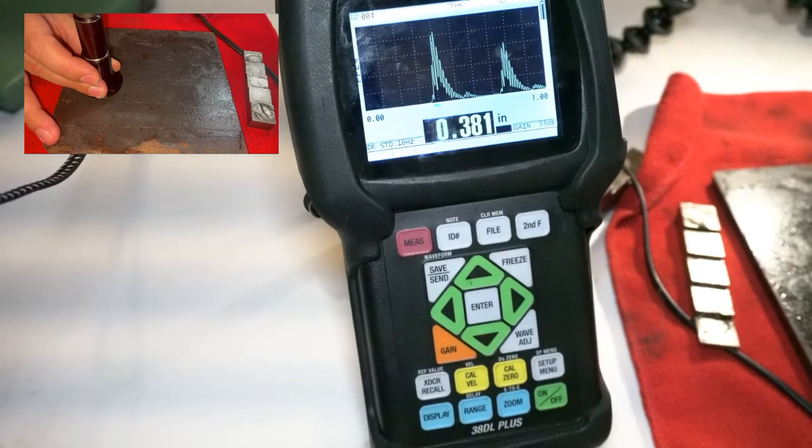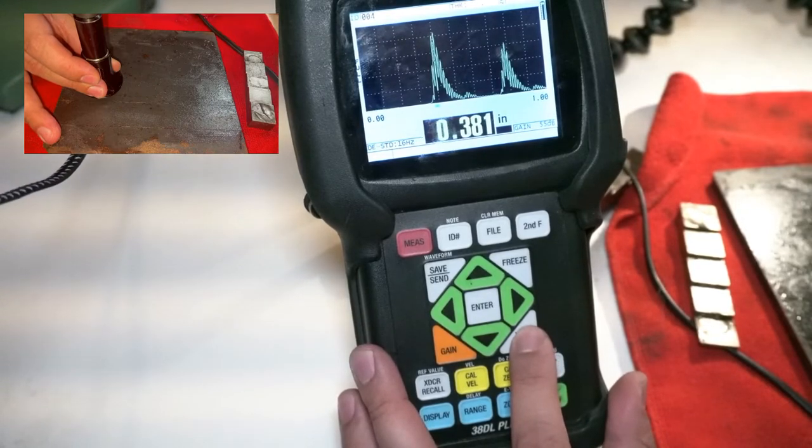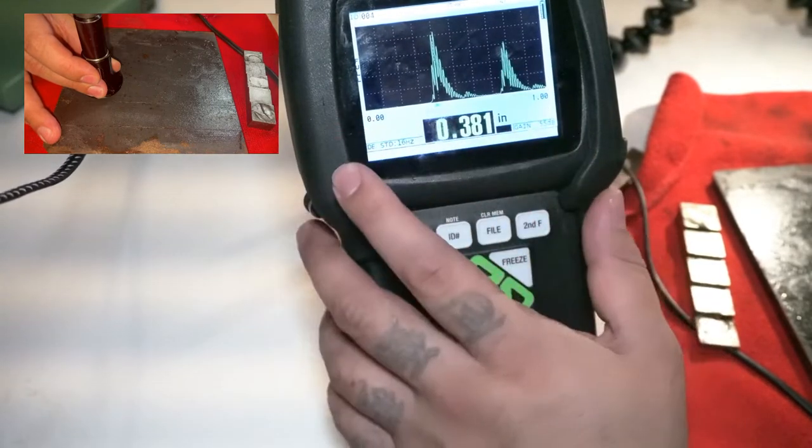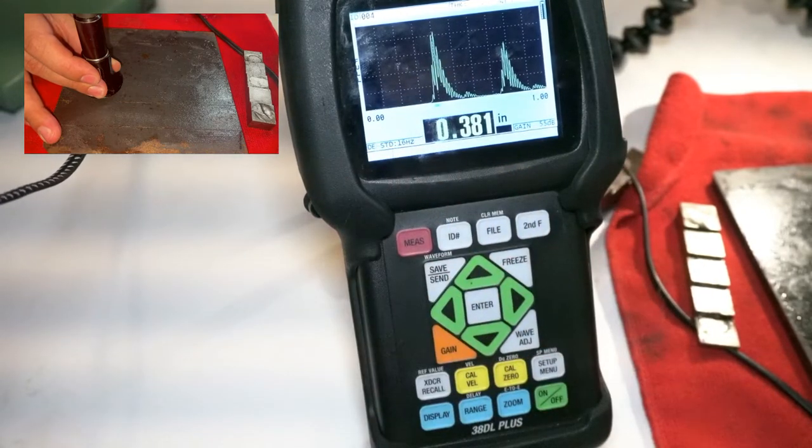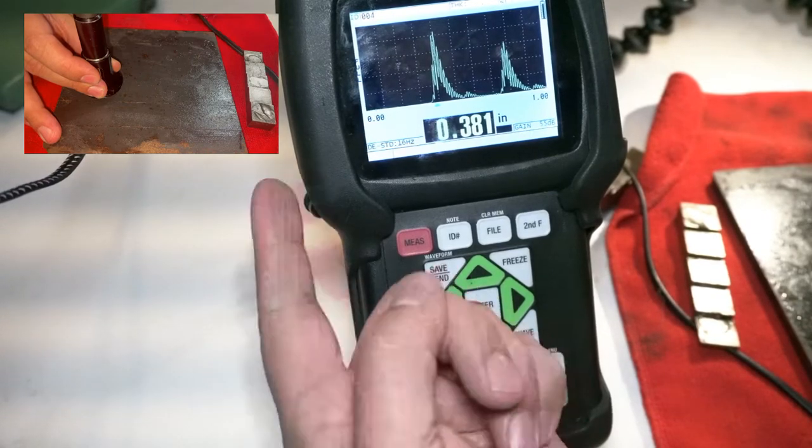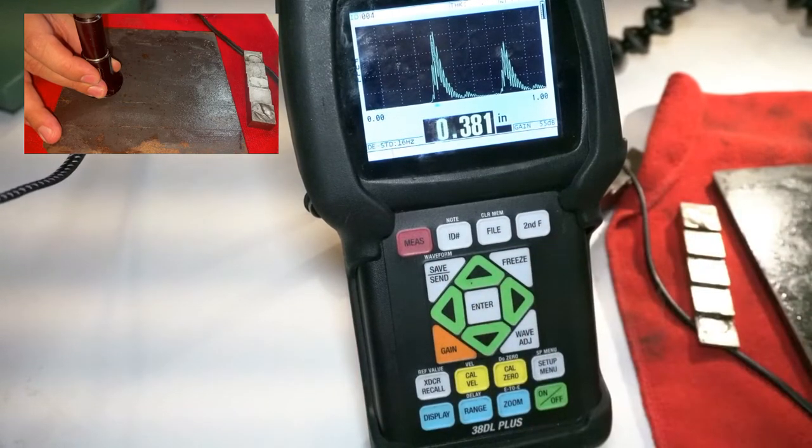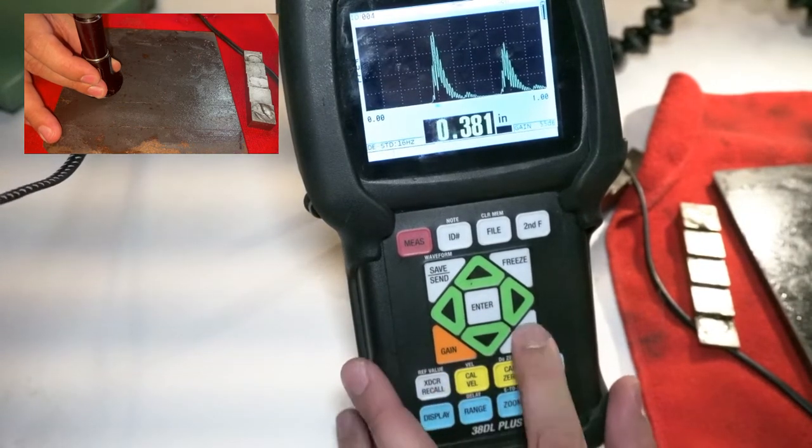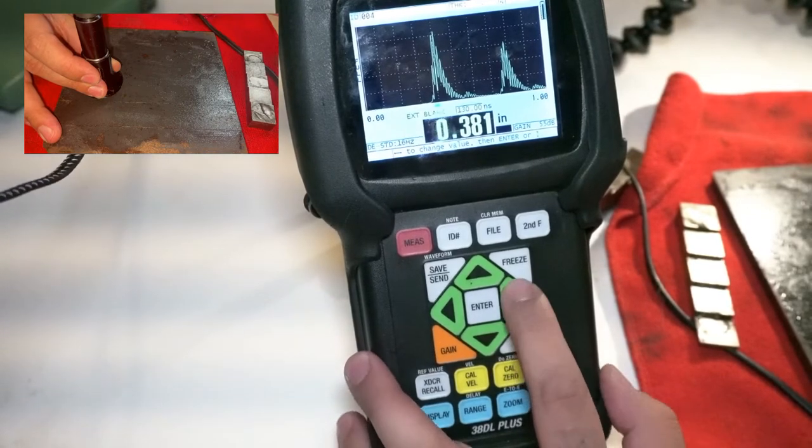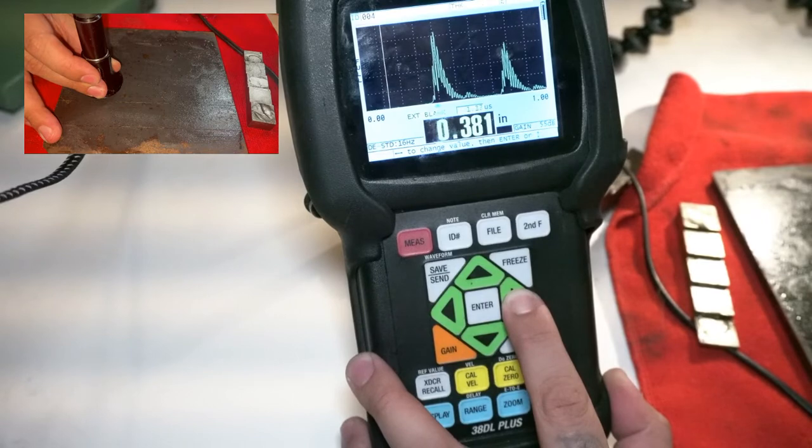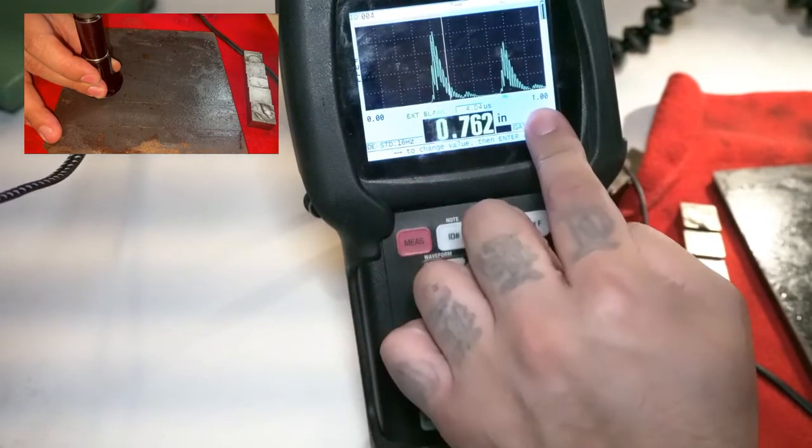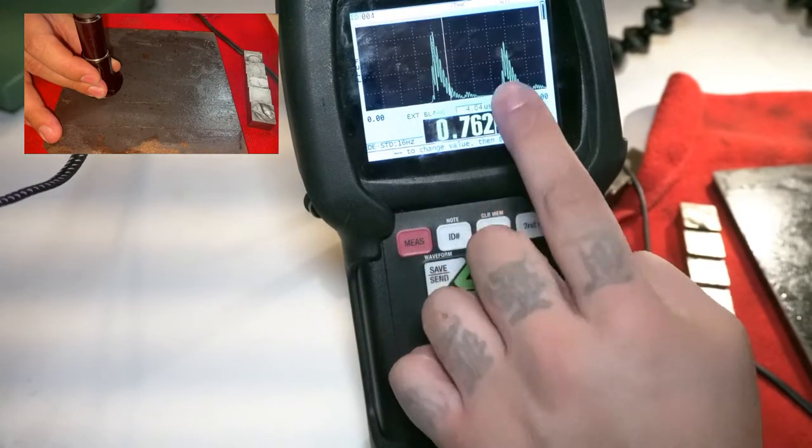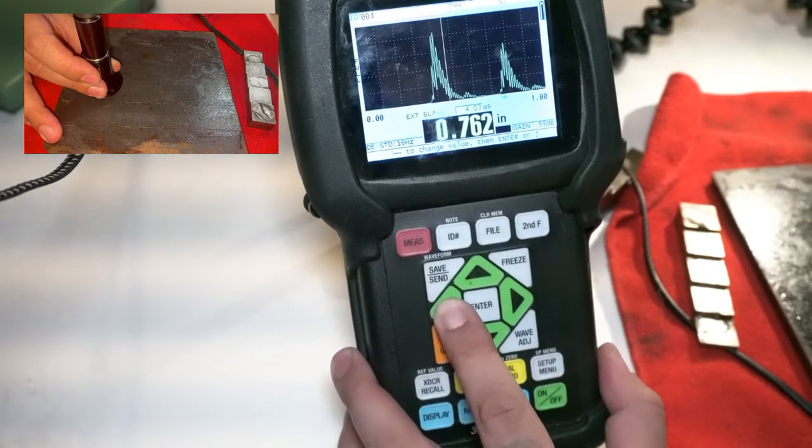One of the other things that they have is what's called wave adjust. Wave adjust allows you to gate separate echoes. So we have our first round trip echo that went through the thickness, hit the back wall and came back to us, and then we had further on in time an additional echo. To validate that echo or to move the gate to that echo we can hit wave adjust here. Adjust our extension blank to where it reads the next highest successive echo and we see here that it's about two times this which is what it should be.